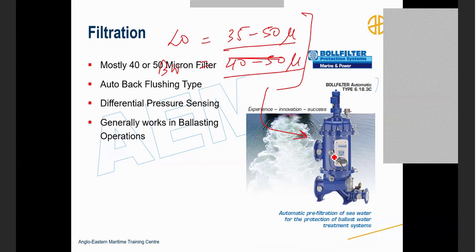And you have got the same differential pressure. So tapping is taken from inlet and outlet, and this is the differential pressure switch, which will initiate a backflush if the filter is getting clogged. So if the filter is getting clogged, you will get differential pressure, and because of differential pressure, you will have a backflush. Though there is no alarm as such for backflush, if the count of backflush is going higher and higher, and differential pressure doesn't come down even after backflush, then there can be an alarm.